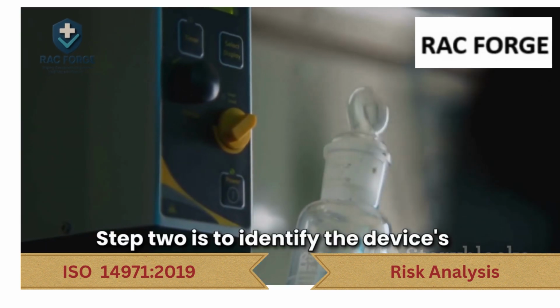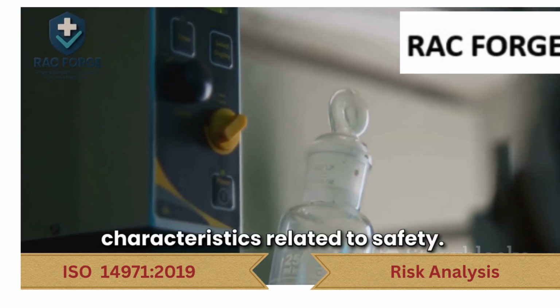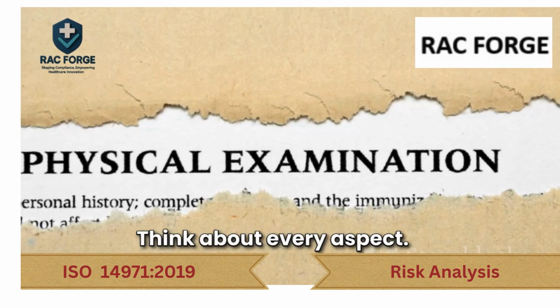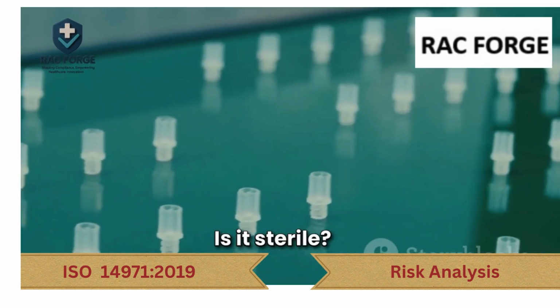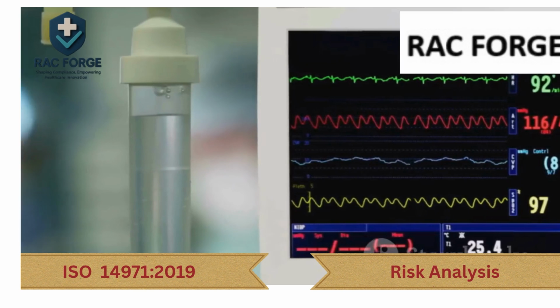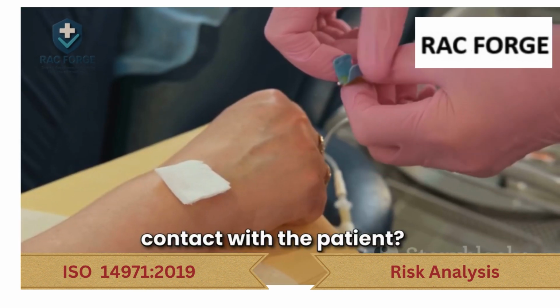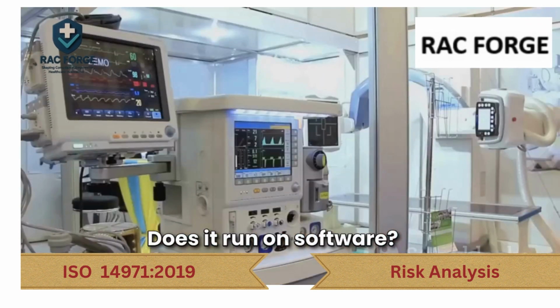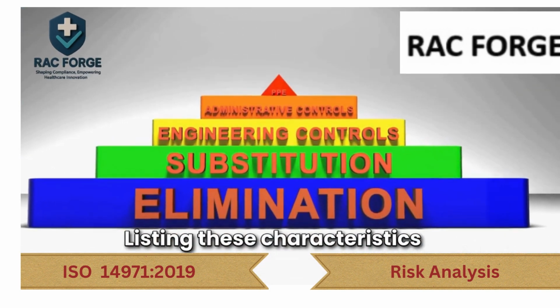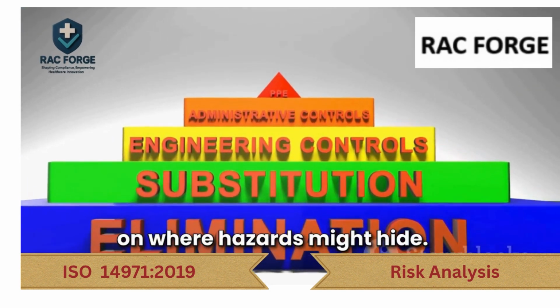Step 2 is to identify the device's characteristics related to safety. Think about every aspect. Is it sterile? Does it use electrical energy? What materials come into contact with the patient? Does it run on software? Listing these characteristics helps you focus on where hazards might hide.